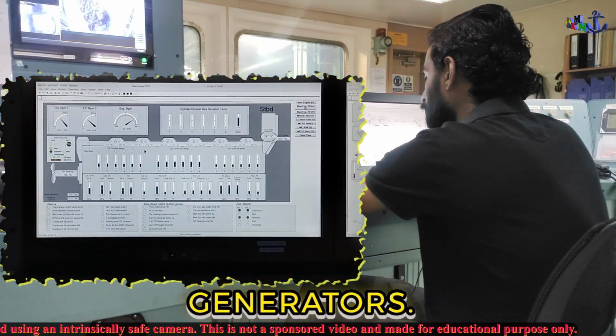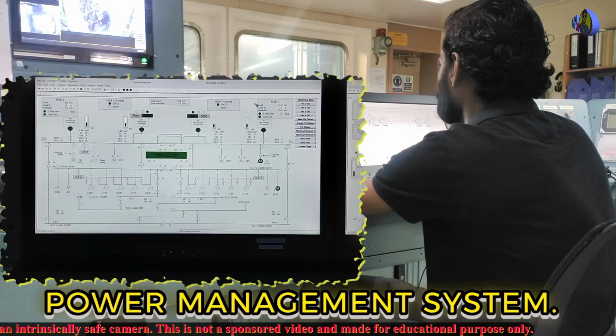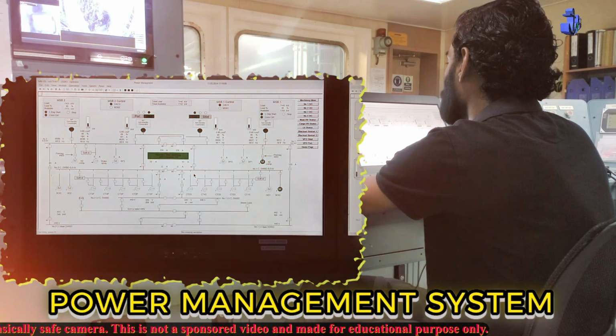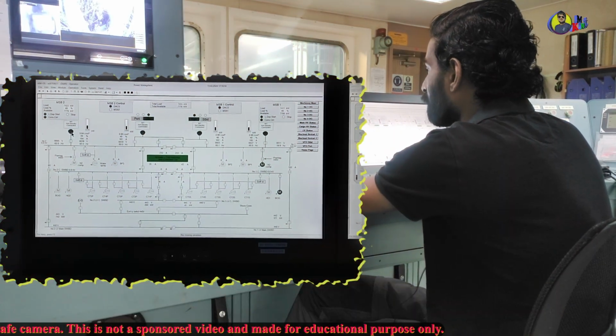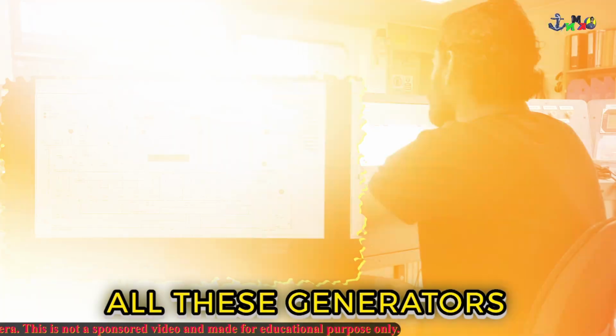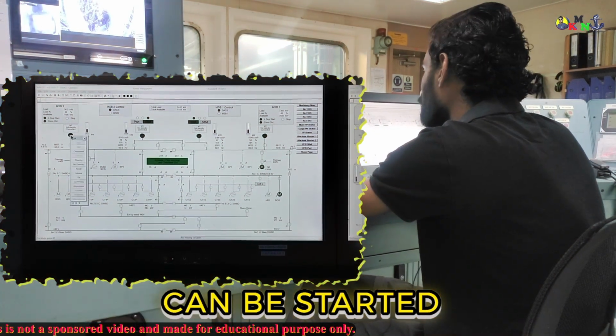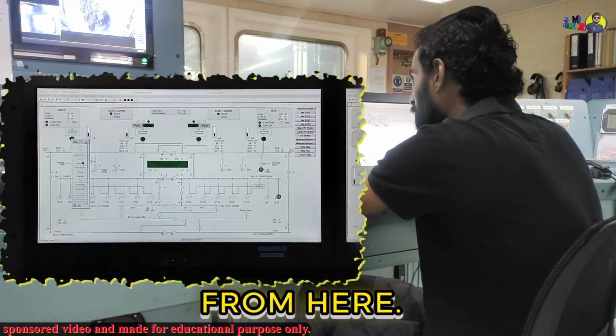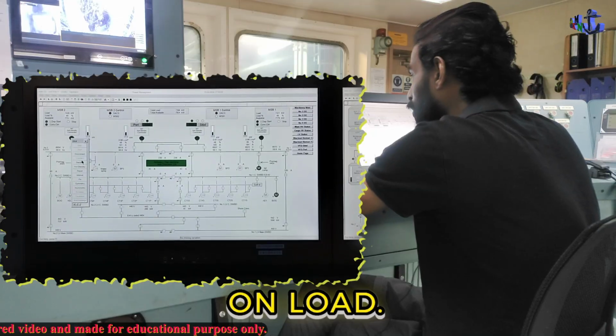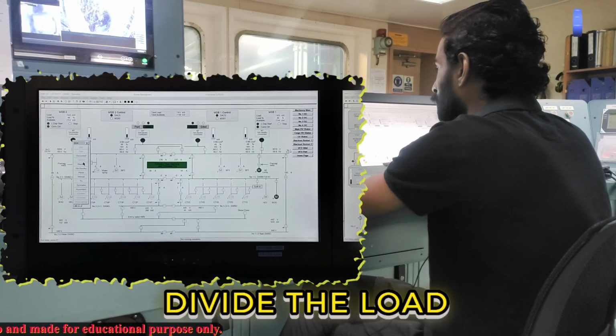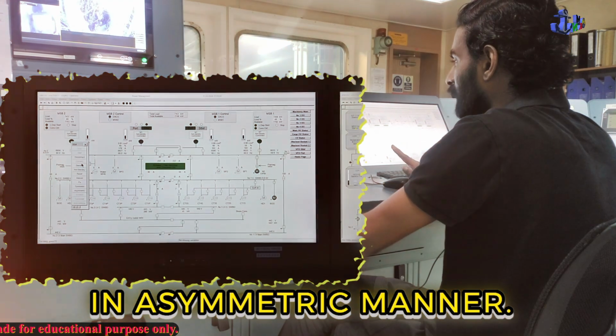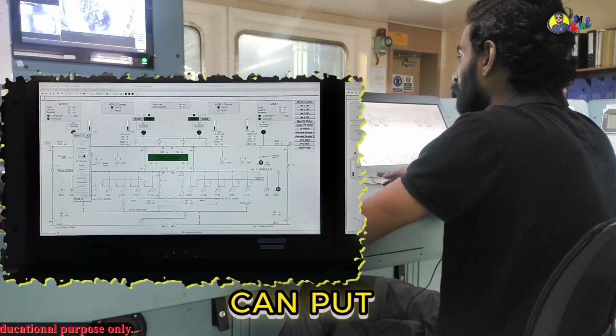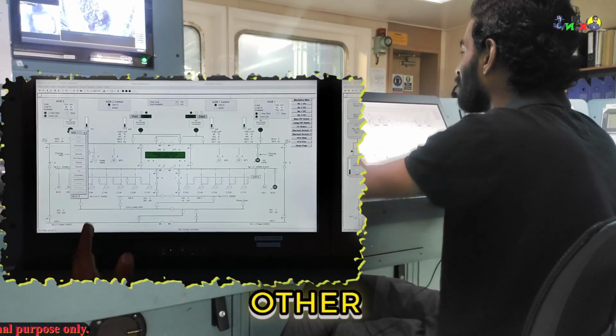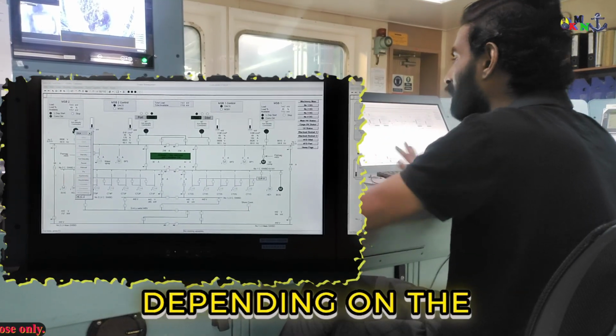Now we'll move to the generators. This is our power management system, and as you can see, we have 4 generators. All these generators can be started or stopped from here, and you can take them on load and divide the load asymmetrically - for example, you can put one generator to 10% and others to 50% depending on the load.